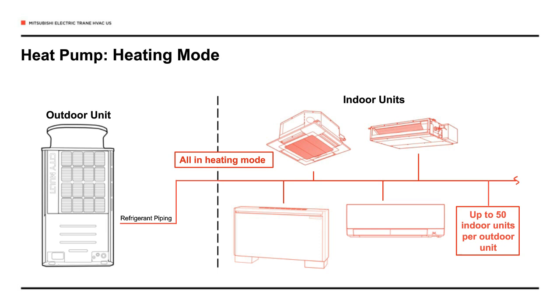Each indoor unit contains a fan, filter, heat exchanger, and temperature sensors for the refrigerant and return air. Indoor units may be ducted, for example, concealed horizontal ducted units, also air handlers are another example, or ductless, like wall-mounted, floor-standing, or ceiling cassettes. In this example you see here, you can see the outdoor unit on the left with refrigerant piping running to a variety of indoor units. And by the way, each outdoor unit has the ability to connect up to 50 indoor units. Each zone can have its own indoor unit that provides cooling and heating. Outdoor units capture heat from the outdoors that is transferred to indoor units during heating. Outdoor units reject heat transferred from the indoor units during cooling. With heat pumps, indoor units are either in all cooling mode or all heating mode. So in this example that you see here, we're showing all the indoor units in heating mode.